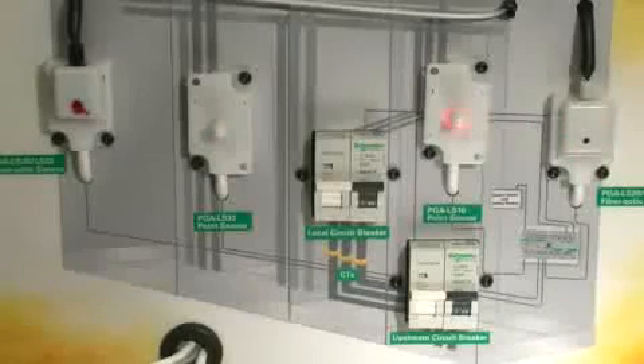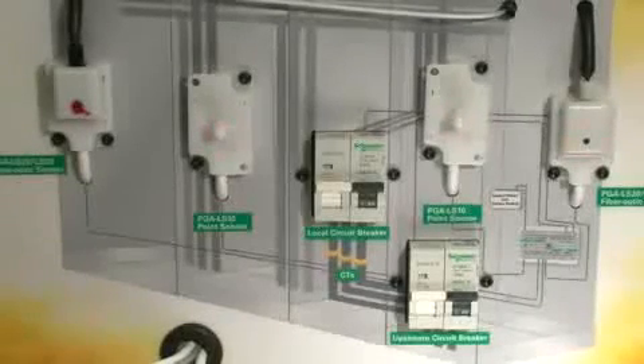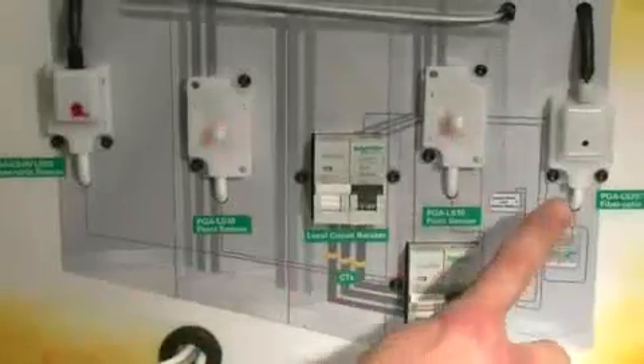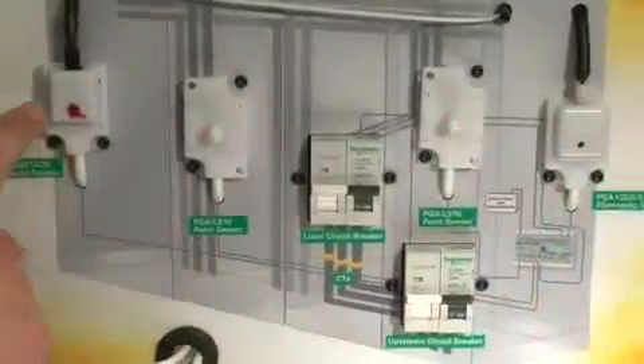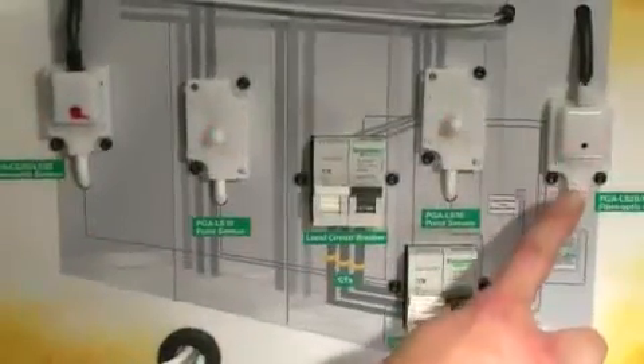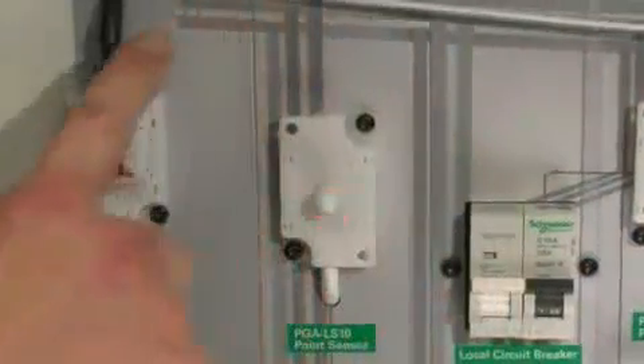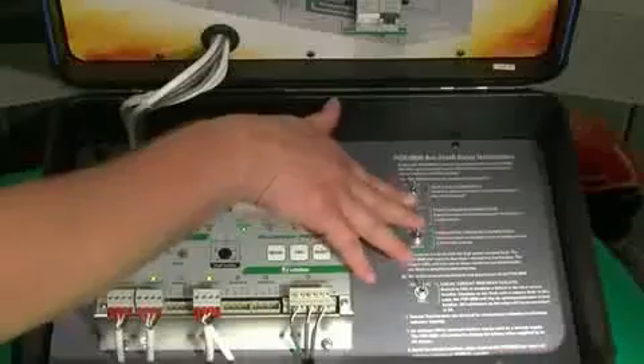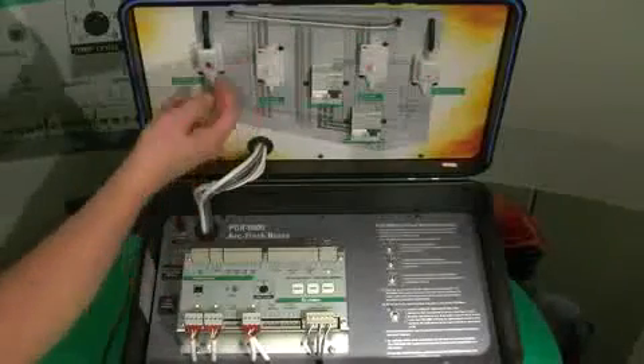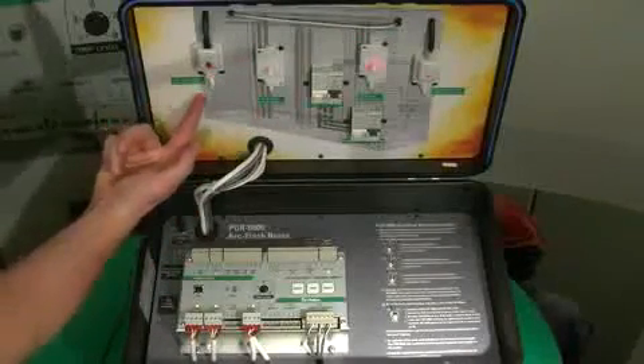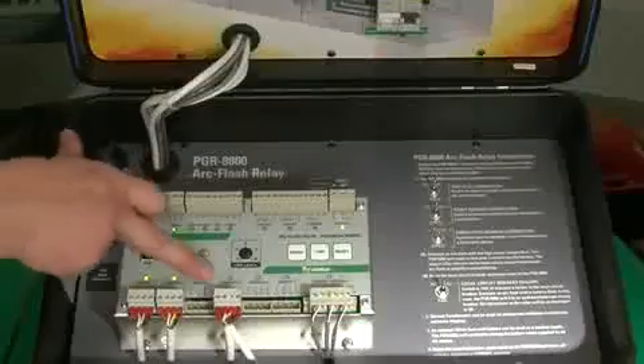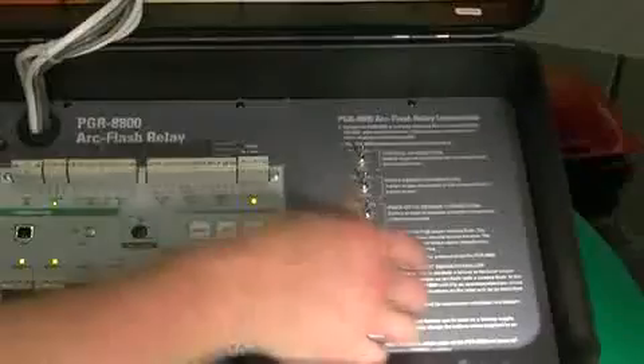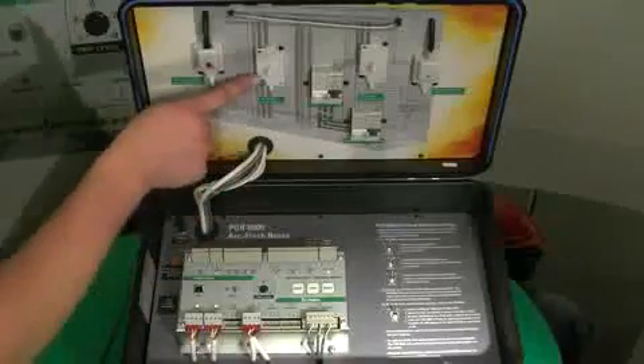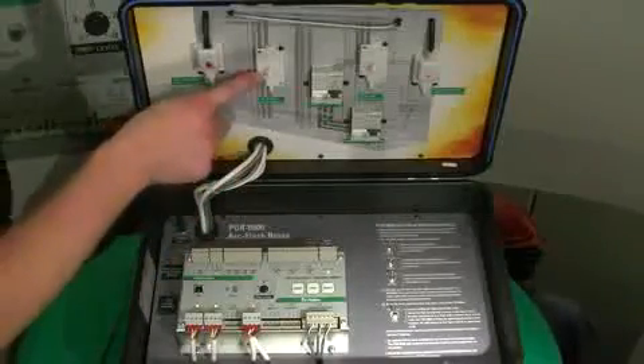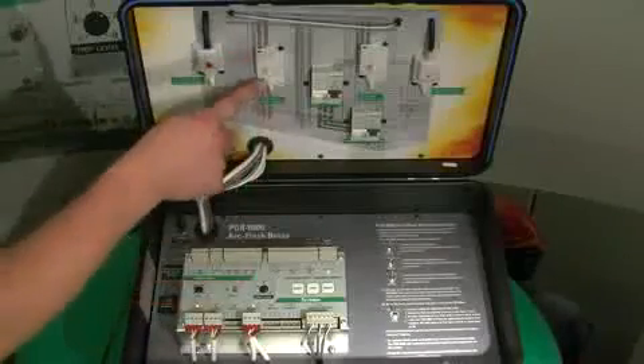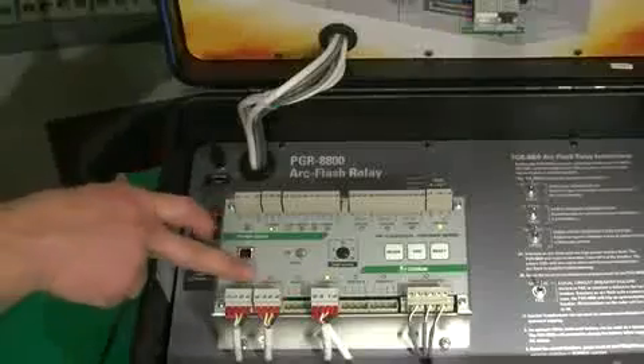The fiber optic sensor also has the same double pulse that you see in our point sensors, but what's happening here is that we have a transmitter and a receiver. So when the double pulse flashes, it goes through the fiber optic cable and it's received on the other end. By turning this switch off, we actually cut the connection with the receiver of the fiber optic cable, and you can see that we have a sensor fault on sensor 4. Same with the point sensors. Here I am disconnecting the point sensor. The unit was sending the signal, it's not getting the red pulse back, so we have a fault on sensor 2.